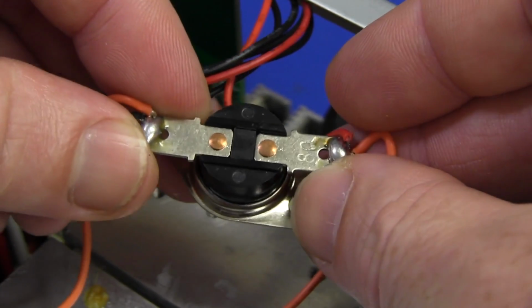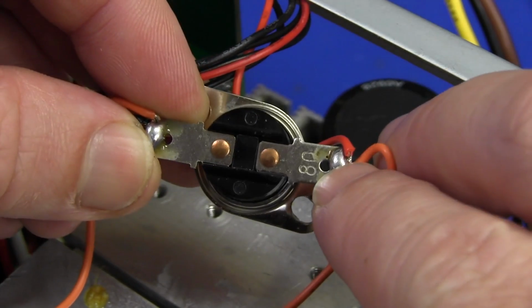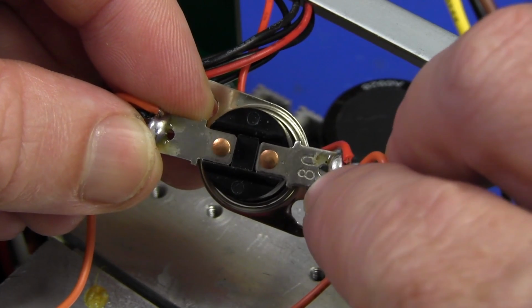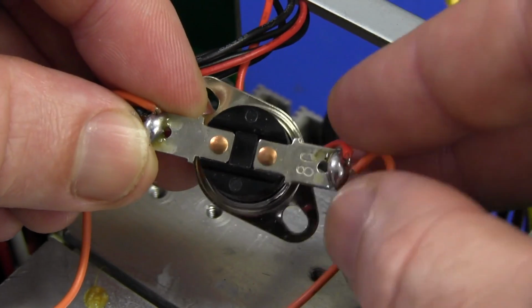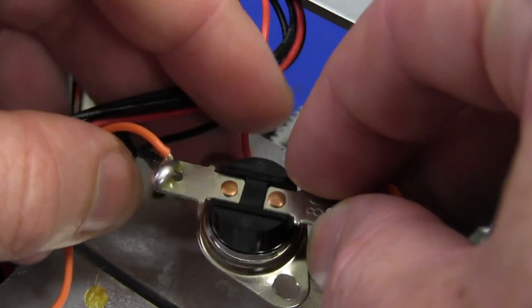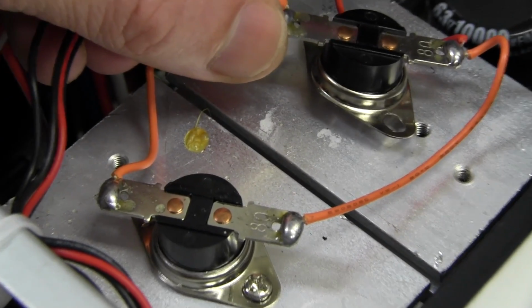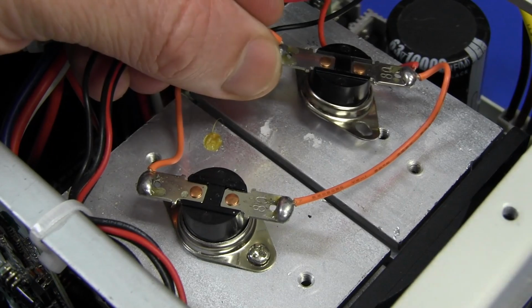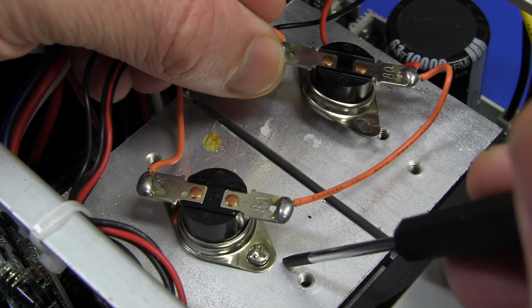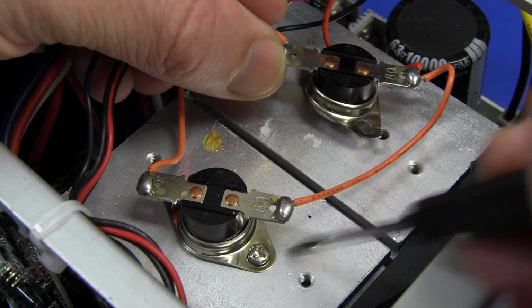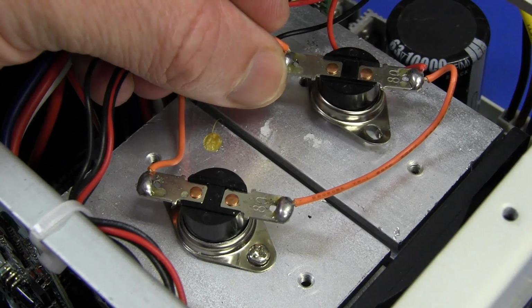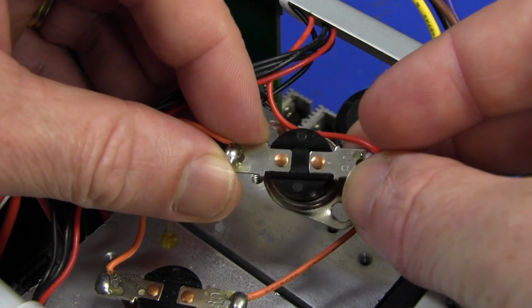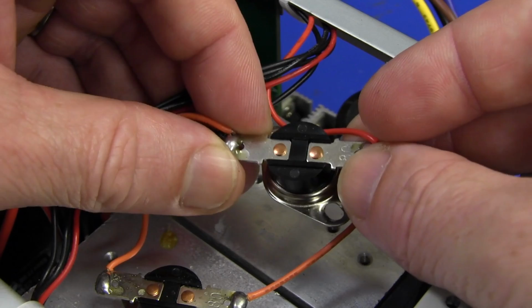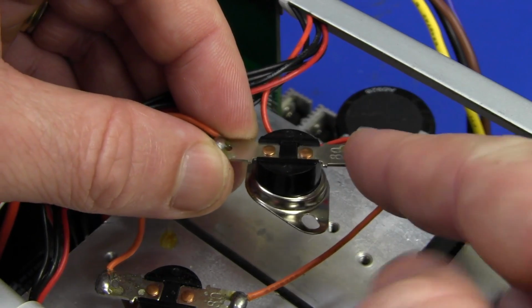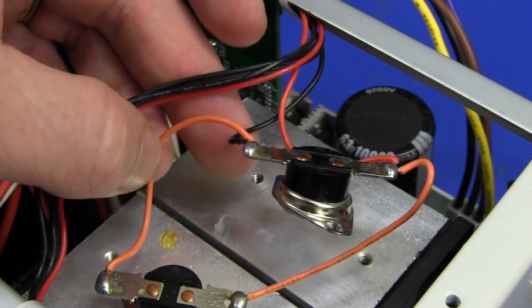Very simple and very reliable. Now, I haven't looked up the data sheet for these, I don't recall, but it's got 80 on there, so I'm going to presume that that's an 80 degrees Celsius cutoff for that. And there's one on each heatsink here. They've actually got two heatsinks, which this one over here is shared between channel 2 and channel 3, and this one's just dedicated to channel 1. Now these are actually a 10 amp rated contact, so they could actually use these to directly switch the output, but they don't, of course.